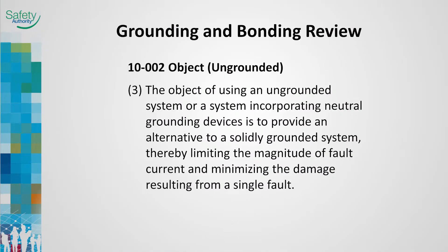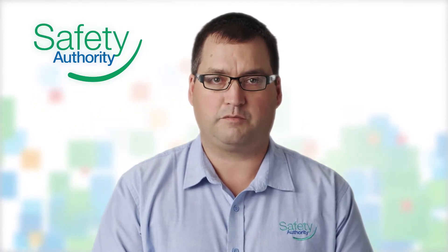Rule 10-002 speaks of using an ungrounded system. Ungrounded and neutral grounding schemes are often installed when some industry processes cannot be interrupted. Usually found on larger installations, qualified electrical maintenance staff will monitor and respond to ground fault conditions prior to a large system fault occurring.